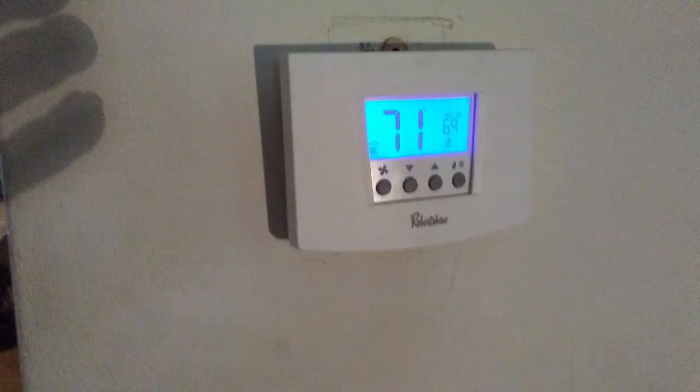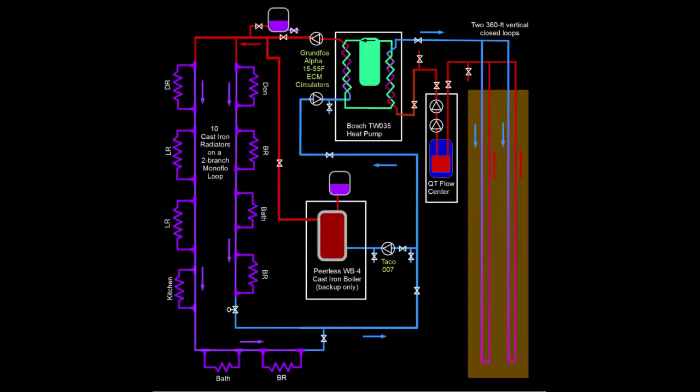The whole system is controlled with this single thermostat, which turns on all four pumps as well as the compressor. Now, if you know anything about hydronic heating systems, you'll notice that what's conspicuously absent here is a buffer tank. The reason is that with all the thermal mass of 10 radiators, you really don't need a buffer tank. In fact, you're better off without one.